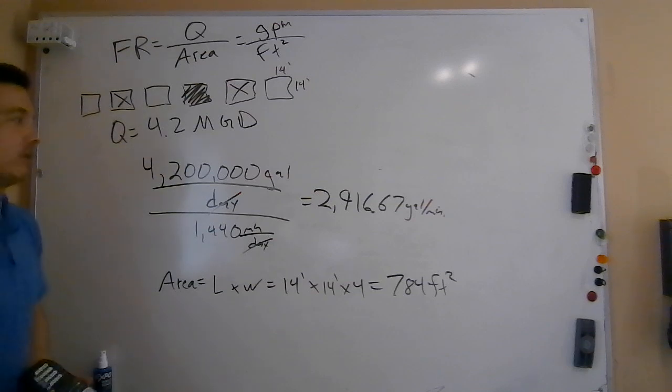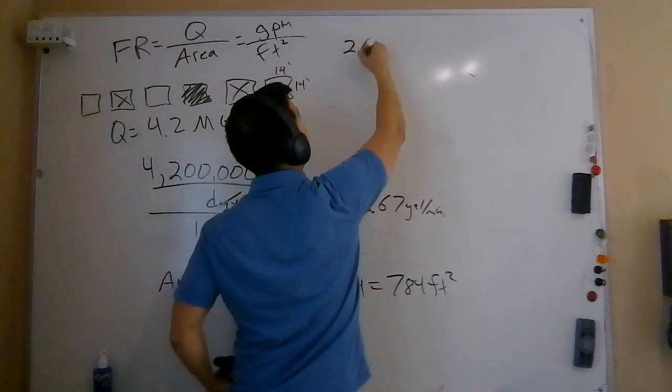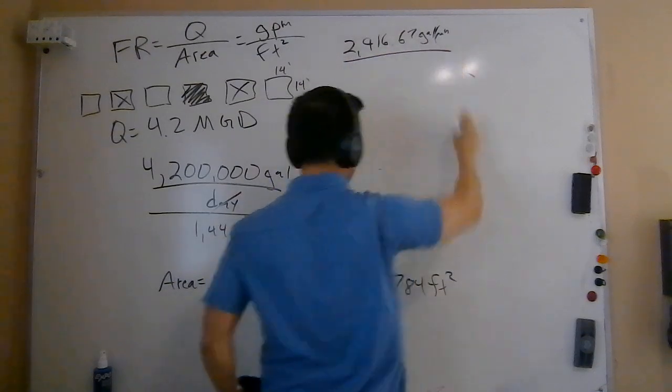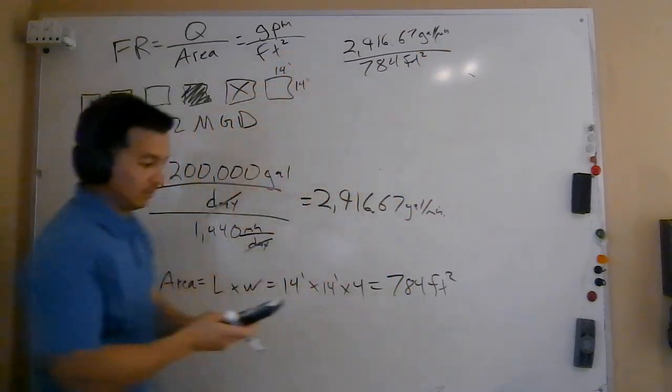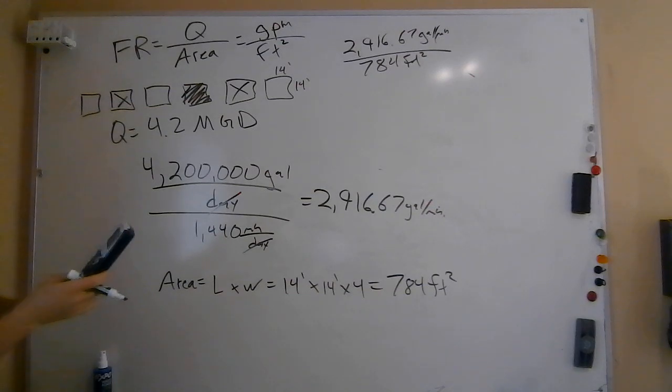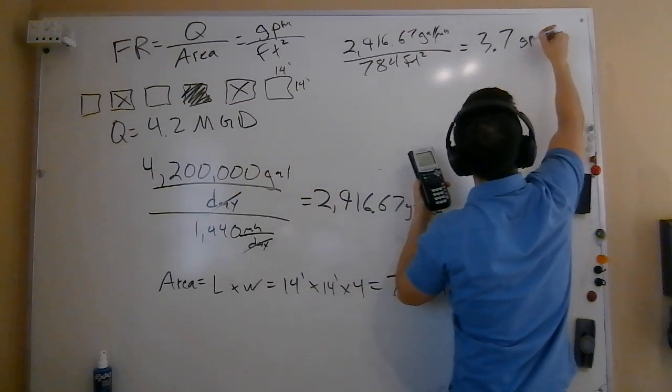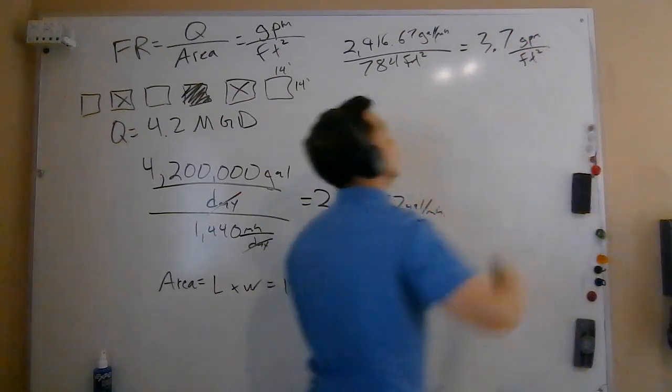So now that I've got my area, I've got my flow. Now I'm going to plug it into my filtration rate formula. If I rewrite it over here, 2,916.67, this is going to be in gallons per minute. I'm going to divide that by my area, 784 square feet, the total area that's treating this total amount of flow. So let's see what we get here. 2,916.67 divided by 784. And I get a filtration rate equal to 3.7 gallons per minute per square foot of area.